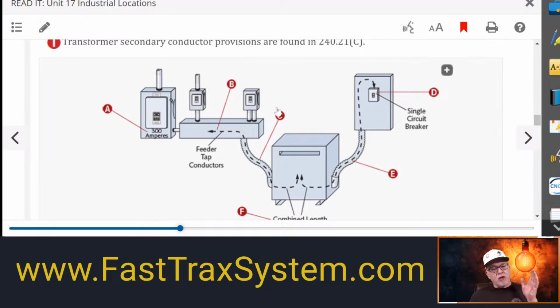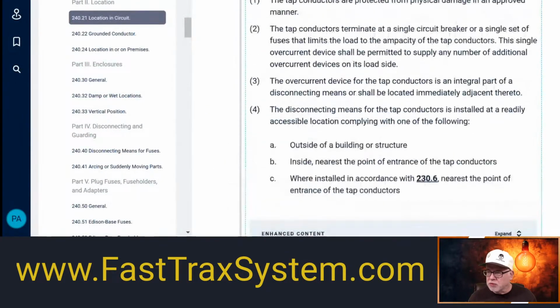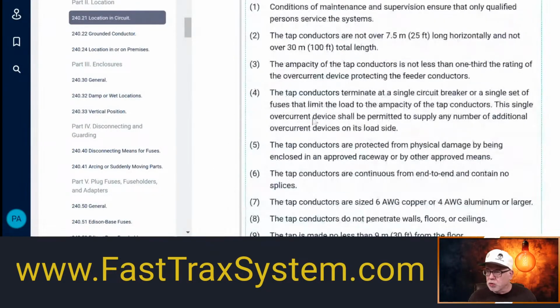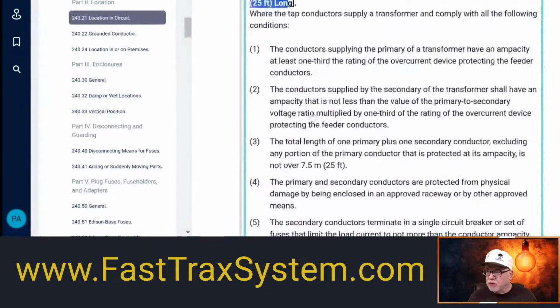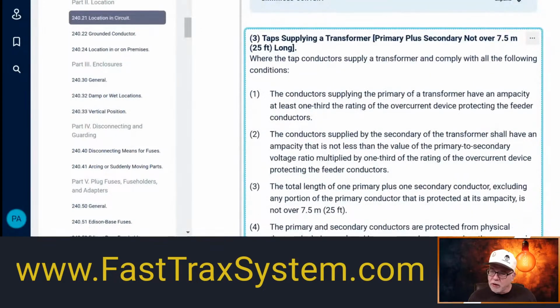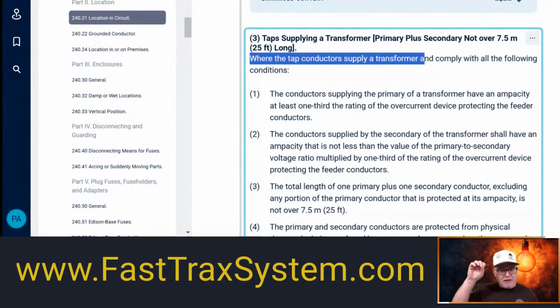Okay? This is also a good example of where you might have multiple voltages in the building now, and now you have to label as such when you have different voltage systems in a building. We talked about that in a previous coffee hour. Okay. All right. So we got to meet some rules here. So let's go back to the rules. What are the rules? All right. So the rules for this one are right here. It says where the tap conductor supplying the transformer, and that is where it tapped it in that wireway down to the transformer.